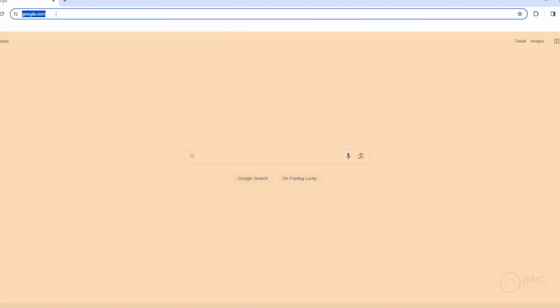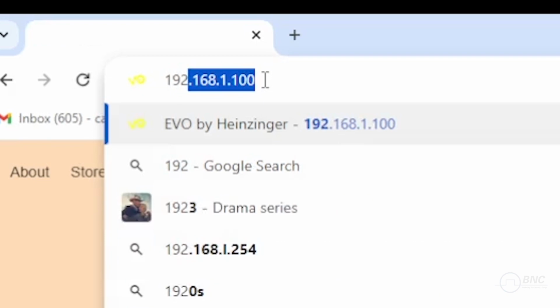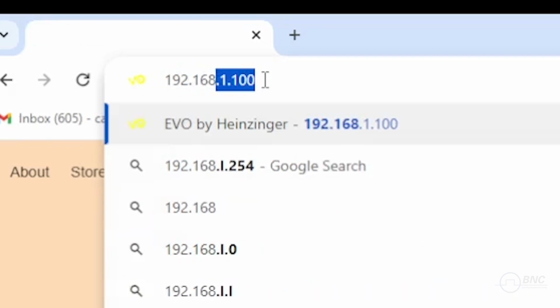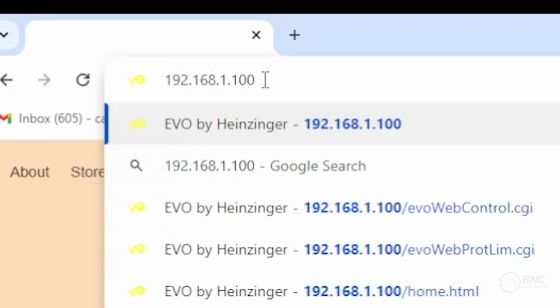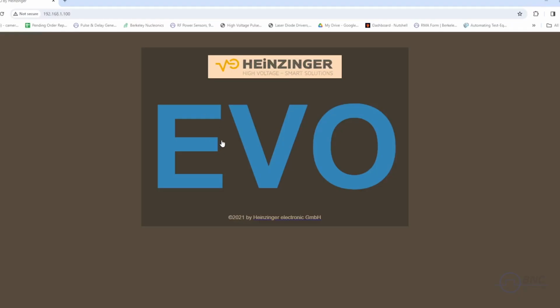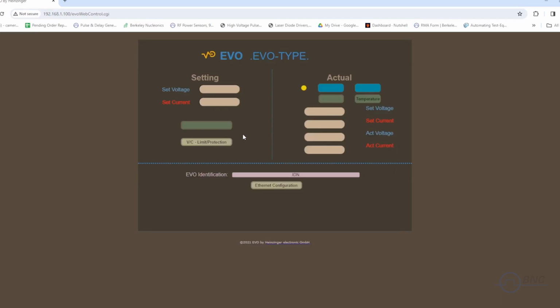Now I'm going to show you how to use the web-based graphical user interface for the Heinzinger EVO. We start by typing in this unit's IP address, set to 192.168.1.100, and we have the home screen here. We click this, it's connecting, and now it's connected automatically, controlling it with Ethernet HTTP. System is okay, temperature is okay, and here we can see our set voltage and actual voltage.